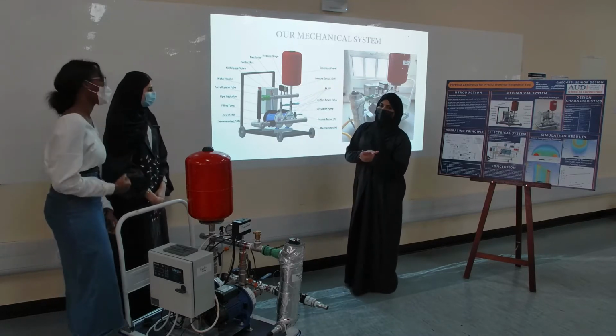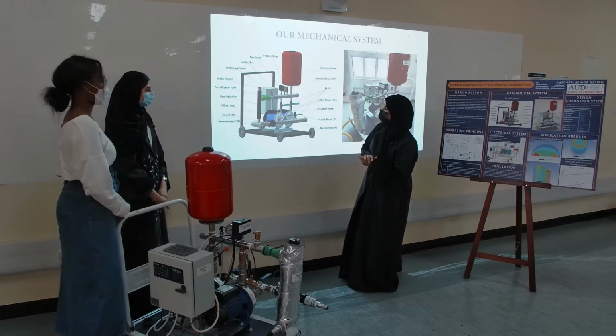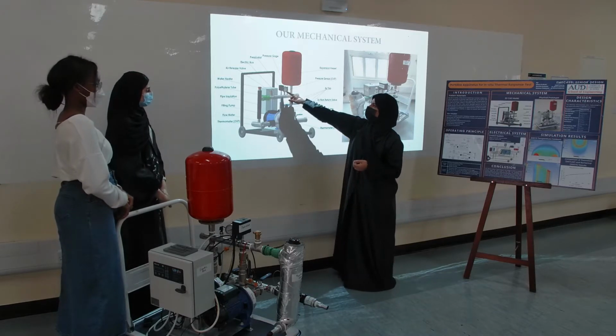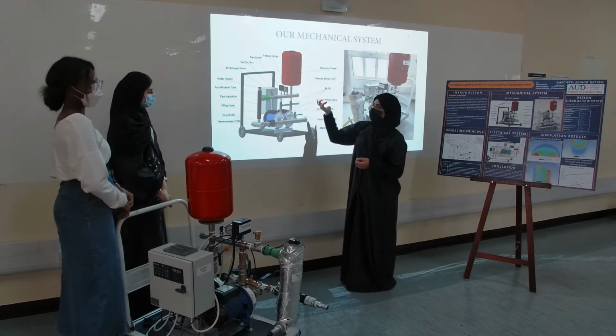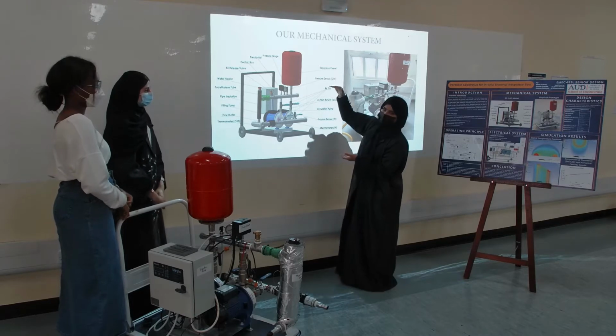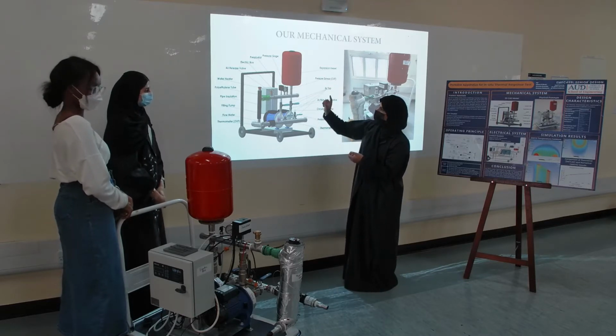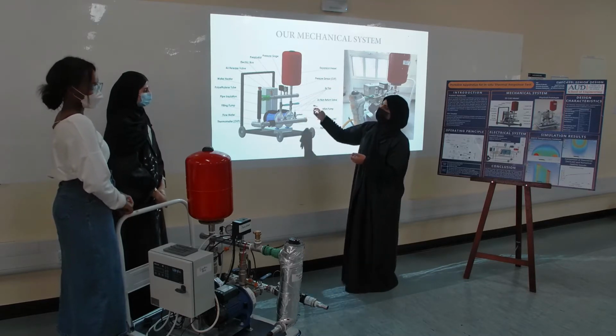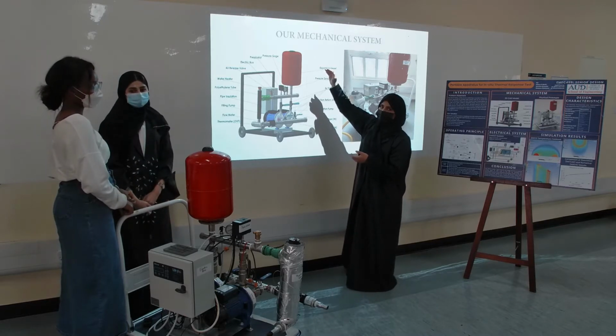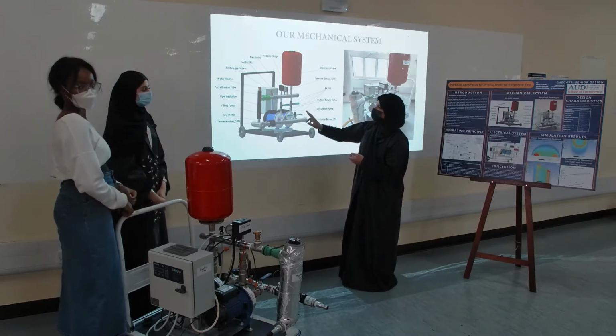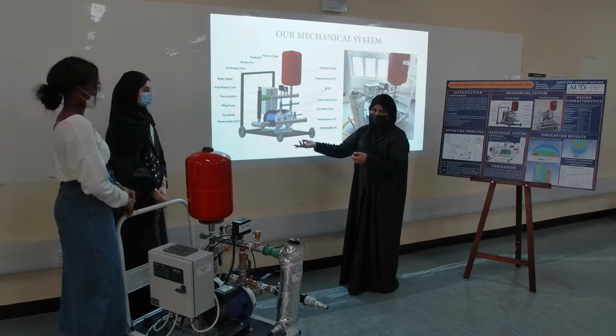The water in the expansion vessel gets pressurized, and here we have a pressure stat. What is the job of the pressure stat? When the pressure drops in the expansion vessel, the pressure stat will turn on the two pumps. If the pressure in the expansion vessel is high enough, the pressure stat will turn off the two pumps.